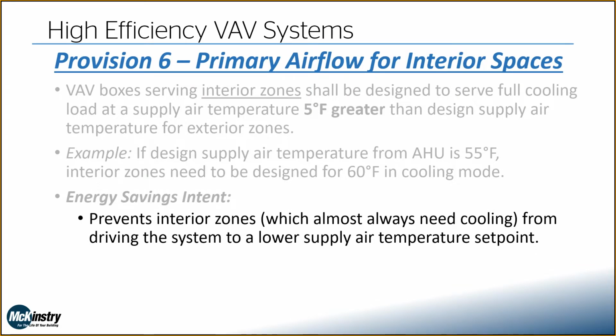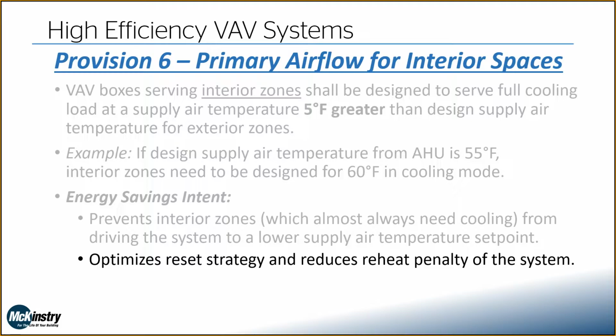The intent here is to prevent our interior zones, which almost always need cooling, from driving the entire system to a lower supply air temperature set point. So really, that's going to optimize our temperature reset strategy and reduce that reheat penalty, which again, that's one of the big reasons for the DOAS provision of the code. They want to limit this reheat penalty inherent with these types of systems.